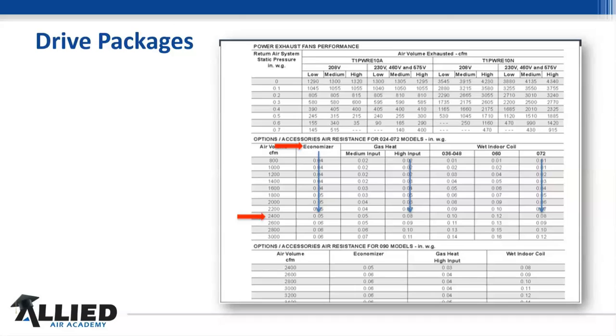but you grab an economizer, well, this chart here that comes out of the instructions and service manual gives you a lot of good information. So you look at your air volume by CFM, and you'll notice from 800 to 3,000, the larger the units you get, the more CFMs you're going to have, obviously. But you'll notice a trend that as you get more CFMs and the larger you get, the more pressure drop that these things are going to cause.